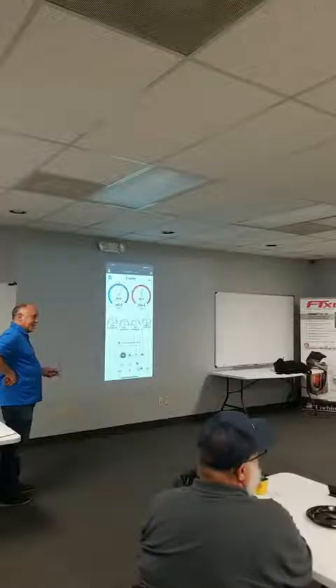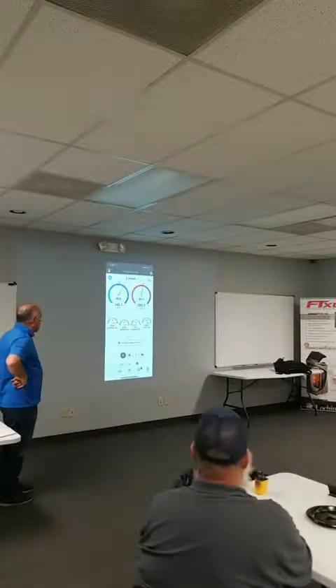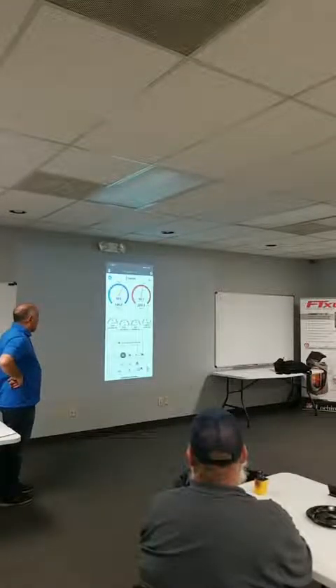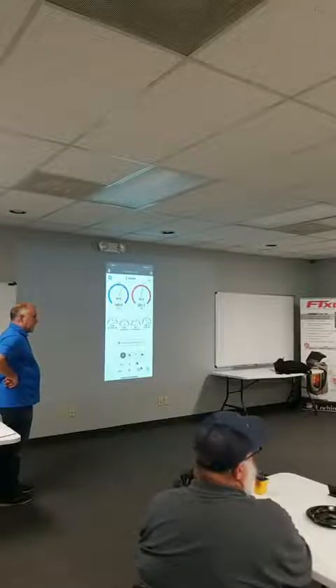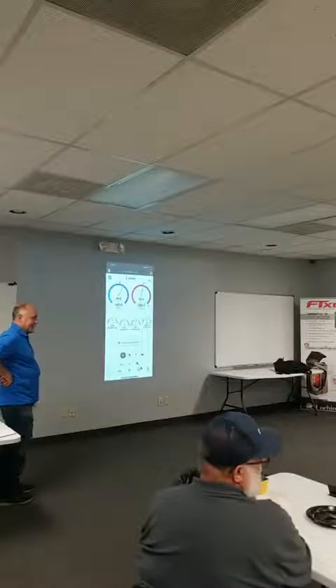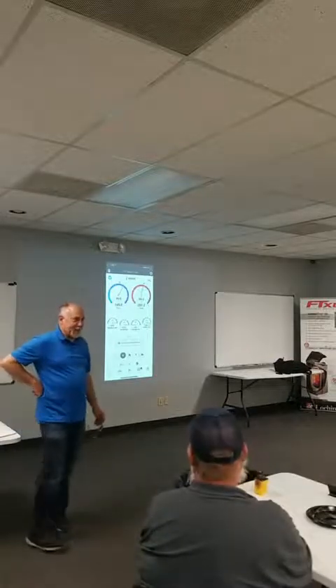Yeah. Wrong place. So, okay, I have to swap the liquid line and the suction line. No, the suction line looks like it's on the liquid line, and the liquid line looks like it's on the discharge line. So we take away the certification.